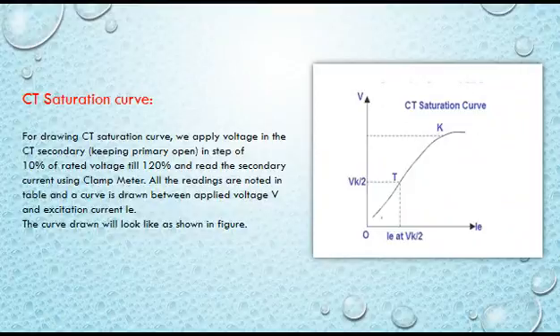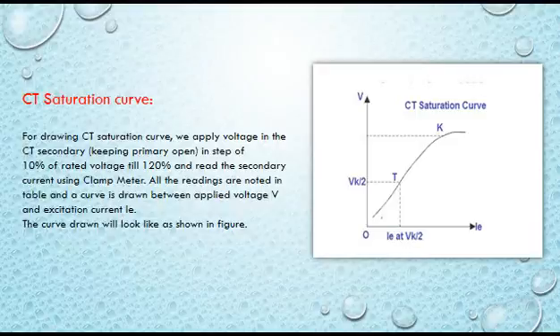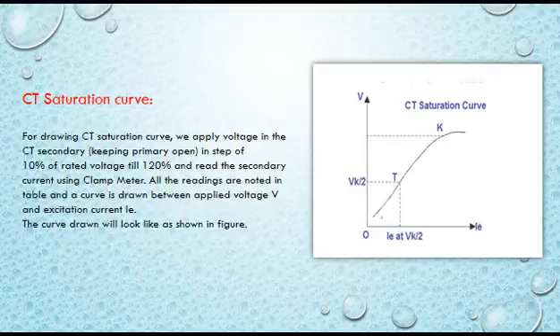Before understanding knee point voltage of a CT or current transformer, you have to understand what is the CT saturation curve. To draw the CT saturation curve, we apply voltage to the CT secondary with the primary side open, in steps of 10% of rated voltage up to 120%, and read the secondary current using a clamp meter. All readings are noted in a table.